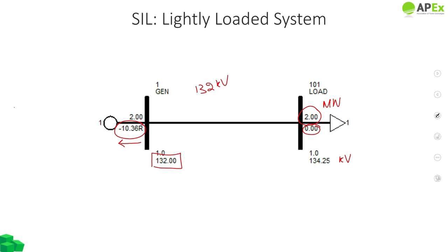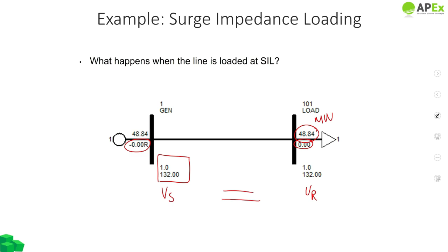Now we will load this line at the surge impedance loading, as shown in the next slide. So we loaded the line at 48.84 megawatts. This line loaded at 48.84 megawatts is neither producing megavars nor consuming megavars, but the megawatts on both sides are essentially the same, which means that the voltage at the sending end, which is 132 kV, equals the voltage at the receiving end. So at surge impedance loading, the sending end voltage is equal to the receiving end voltage.